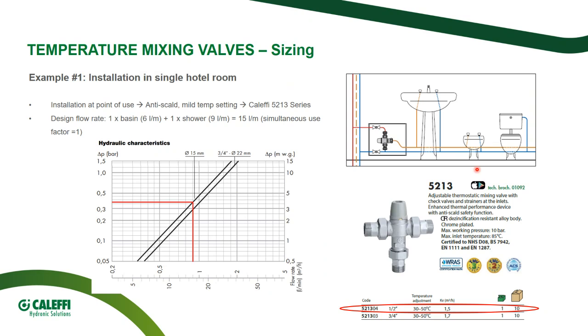Let's consider a couple of examples. Let's consider a hotel where the designer decided to have a thermostatic mixing valve serving the single washroom, so is selecting an installation at the point of use. Installation at the point of use will require certain features, so an anti-scald feature and a mild temperature setting, because it is the last protection before the user. So, for instance, we identified the Caleffi 5213 series. This series is available in 1/2 inch, 3/4 and 1 inch. You don't see 1 inch here because it's the news of the year, but we have to select the proper size. So let's calculate it.